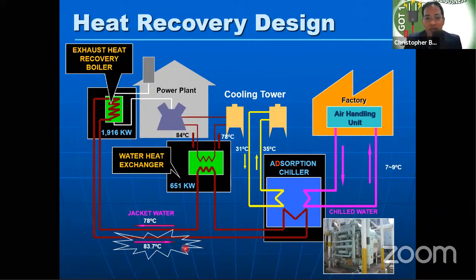So saan naman namin ginamit yon? As mentioned, we have installed an absorption chiller. So what is an absorption chiller? Actually, this is like a chiller system, an aircon system, a water system aircon system, where you will just use hot water to generate chilled water of 7 to 9 degrees C. Imagine, ako, hindi rin ako makapaniwala, no? Meron palang ganung equipment during my time. So hot water lang, and you can generate chilled water without electricity, without using any energy from compressors, di ba?